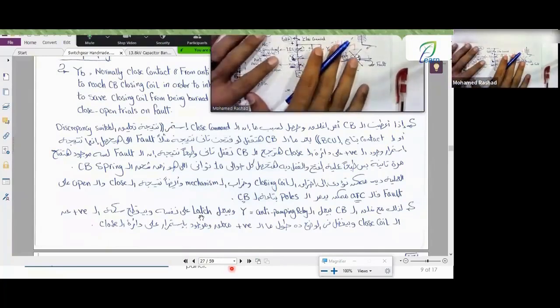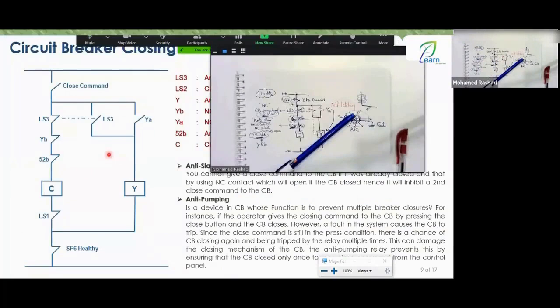This process could lead to the burning of the closing coil and damage to the mechanism. Also, as a result of closing and opening on a fault, this arc could destroy the poles of the circuit breaker. This is what is referred to as anti-pumping. Therefore, when the circuit breaker closes, the anti-pumping mechanism latches onto itself and cuts off the DC path, specifically the positive, from the closing coil, and remains in this state as long as the positive is continuously applied and present on the closing circuit. So I have now explained to you the concept of the anti-pumping mechanism.